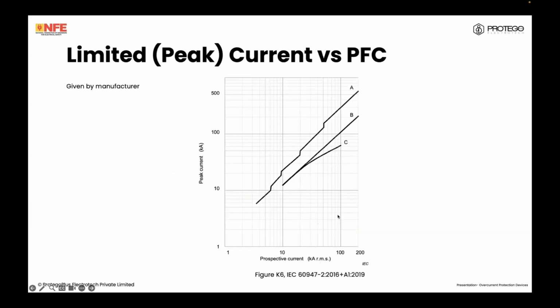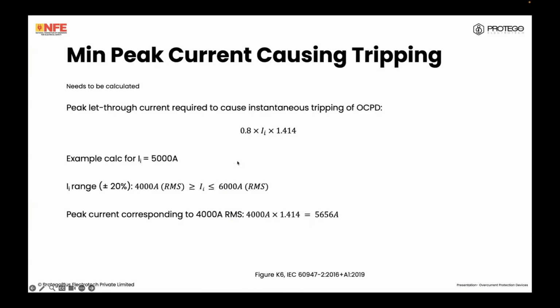So say if I have 100 kiloamperes, obviously you're coming into ACBs and stuff like that, or say 10 kiloamperes. This is the amount of peak current that will be seen by the upstream circuit breaker and wiring system. This value has to be less than the minimum peak current causing tripping. Okay. Now, say I've got an MCCB that is set to trip at 5000 amps. So for instance, say it is a 500 ampere MCCB and it is set to an instantaneous tripping setting of 5 times 10, so 5000 amps. It's important to know that in these adjustable circuit breakers, 60947 requires us to take into account a tolerance of plus or minus 20%, which means the minimum peak current can only be calculated when we multiply this by 0.8, which is 20% less. So we take 4000 amps. So 5000 multiplied by 0.8 is 4000.